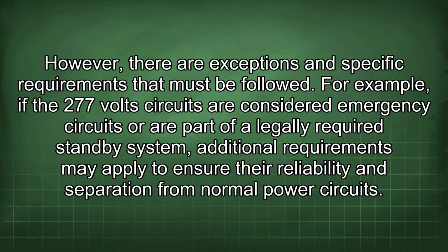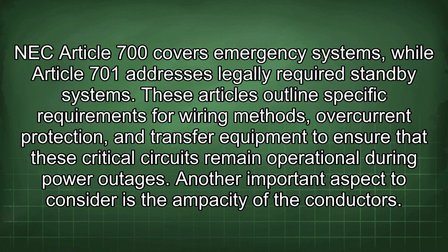For example, if the 277 volt circuits are considered emergency circuits or a part of a legally required standby system, additional requirements may apply to ensure their reliability and separation from normal power circuits. NEC Article 700 covers emergency systems, while Article 701 addresses legally required standby systems. These articles outline specific requirements for wiring methods, overcurrent protection, and transfer equipment to ensure that these critical circuits remain operational during power outages. Another important aspect to consider is the ampacity of the conductors.